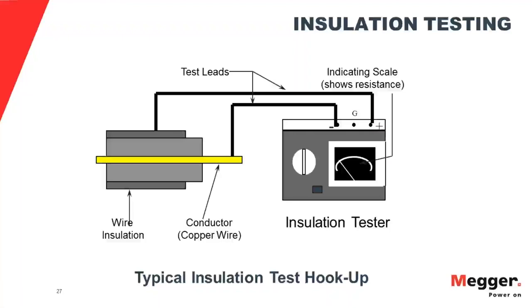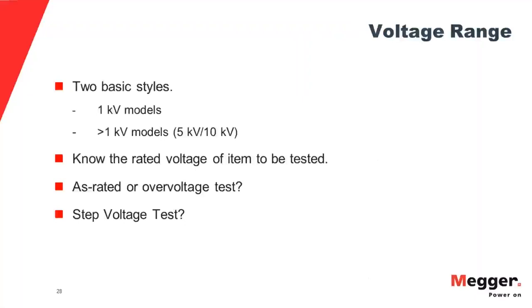And then when you energize the tester, you now have a voltage between those two terminals, and leakage current is going to travel through the insulation from one terminal to the other. The tester is going to measure that and convert it into the resistance of that particular insulation. And note, typically the instruments are divided at the 1 kV level. So for all your building wiring requirements, 120, 240, 480, 600 volt circuits, all you need is a 1 kV tester. You can then test at around rated, and if you want to do a stress test looking for problems, you can do twice rated. And a 1 kV instrument is fine.